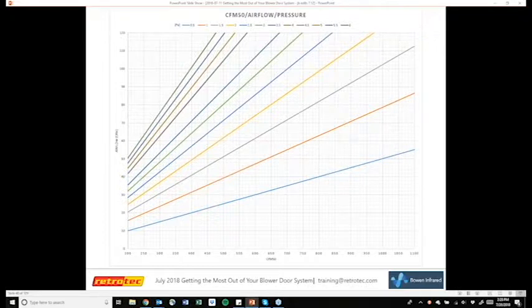So what you do is turn the air handler fan on, no heating or cooling, just have the fan running, with the ventilation damper shut or taped off, and have your manometer reading the indoor pressure with respect to outside. Then stop the test, record your reading, and run it again with the ventilation damper open. It should be a positive difference because you're bringing air into the house, and with a positively pressurized system you don't have any way to exhaust stale air. It's just bringing new air in, so it should be a little bit more positive.